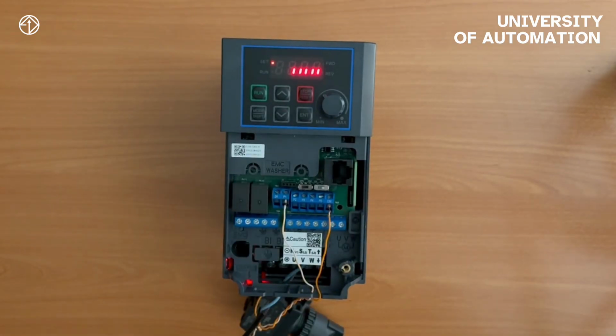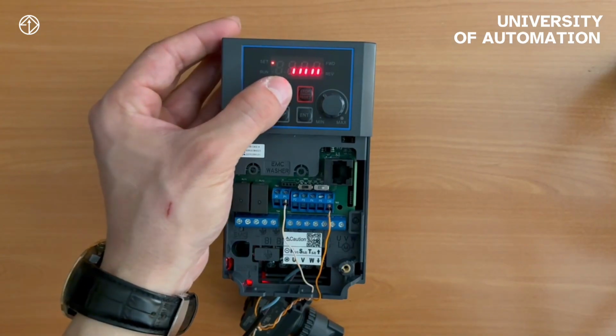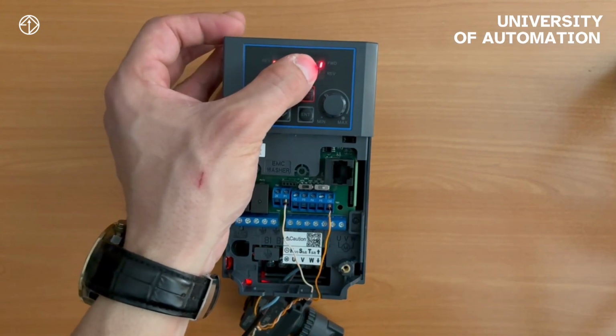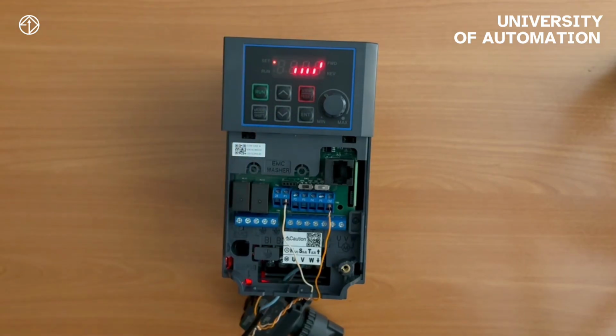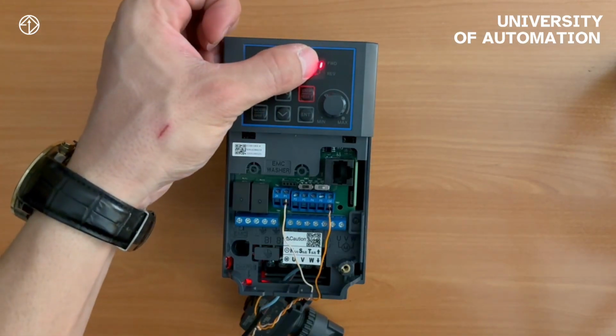If we want one of our digital inputs to be in normally closed mode, the corresponding bit must be active, meaning it should be high. If the corresponding bit is low, that digital input will be in normal mode. If this bit is high in parameter 87, it will be normally closed. If the bit is low, it will be normally open.